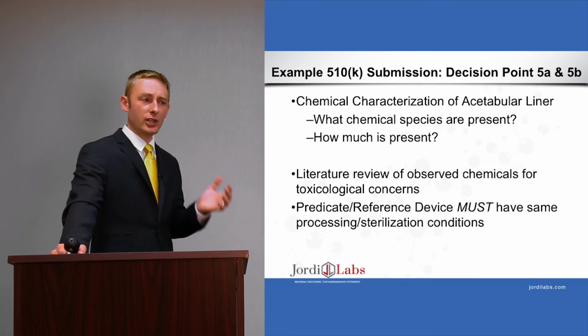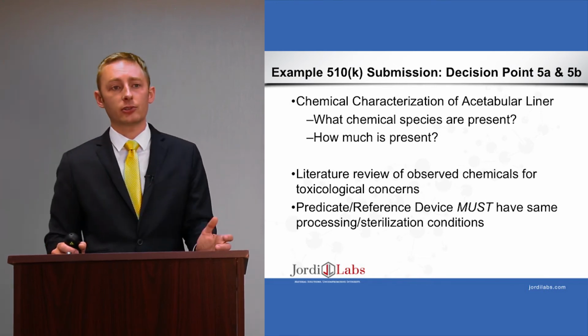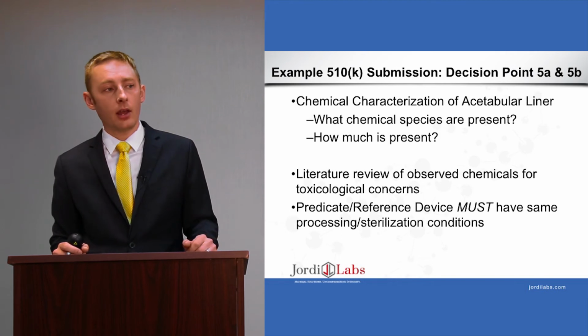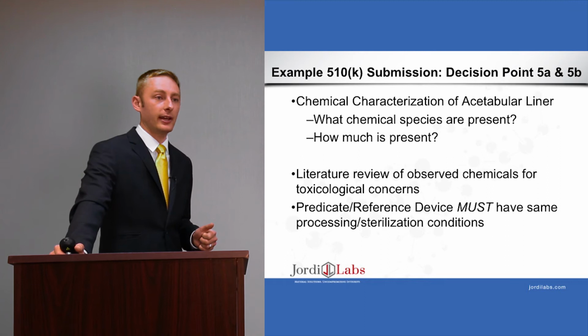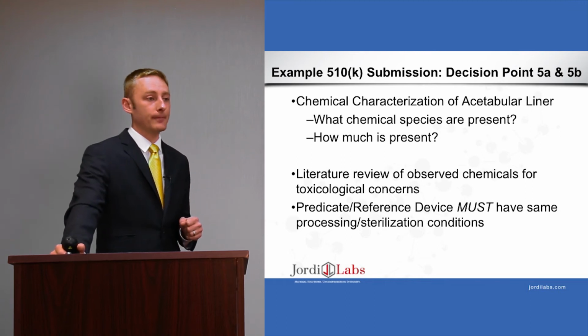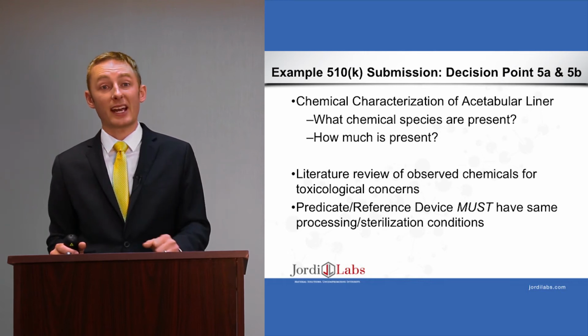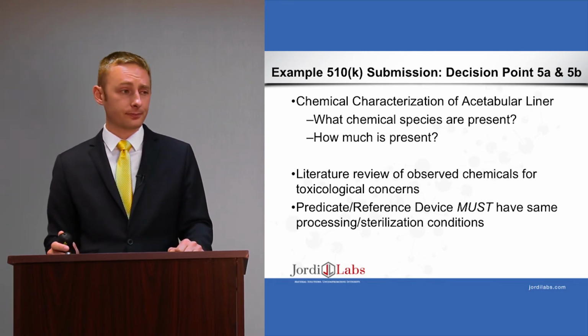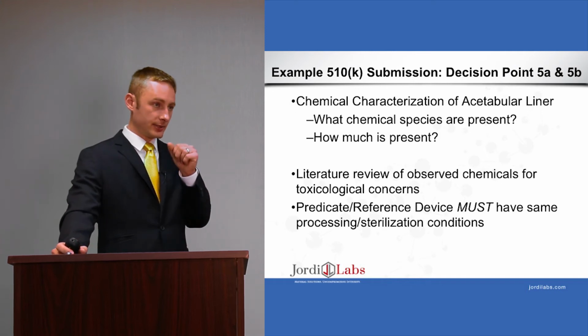That's very important, because if you change the sterilization conditions, very frequently you introduce new vectors for concern. There's an excellent webinar by the FDA where they go over sterilization in great detail. But the point is that your predicate and your reference device have to have the same things done to them to ensure that there are no new questions of safety and efficacy.